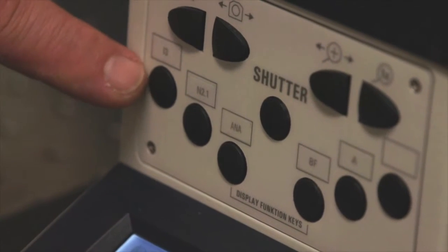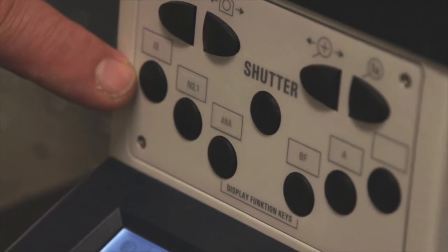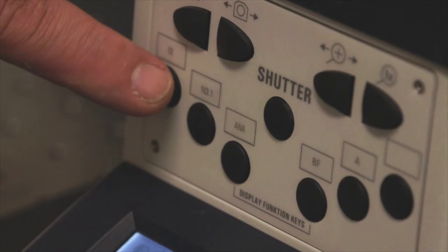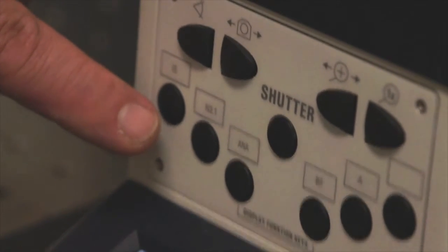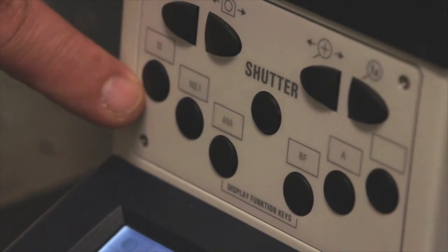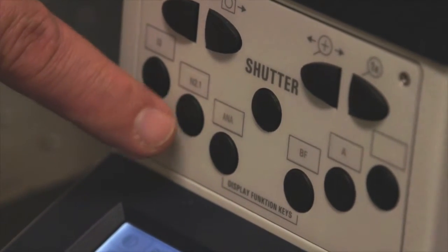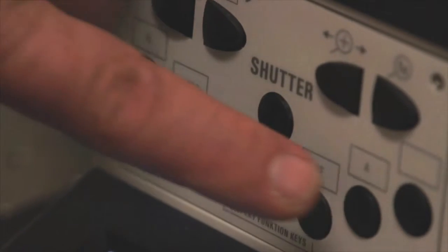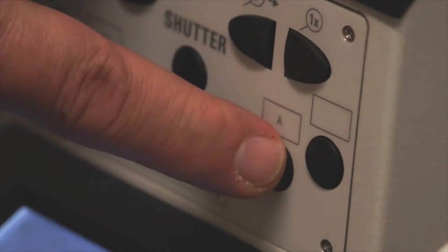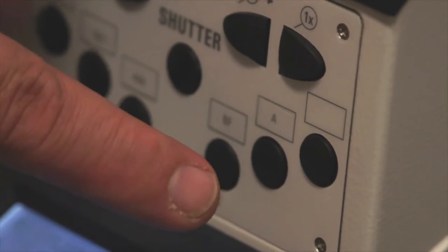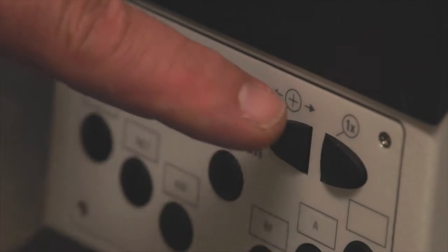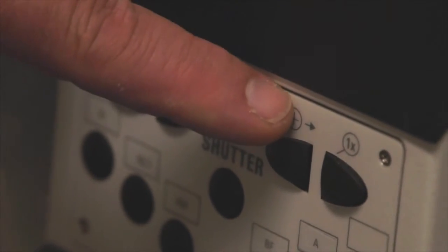To actuate the filter packs inside the microscope, you press the buttons on the front of the microscope, which allow you to select one of the 4 filter packages. This button is for FITC, this button is for rhodamine, this button is for DAPI, and this button is for green fluorescent protein. Do not touch these two buttons on the front of the microscope, and only rarely will you actuate one of these buttons, which we will discuss at a later date.